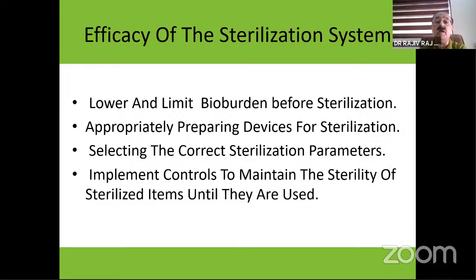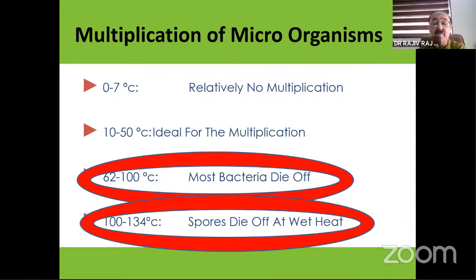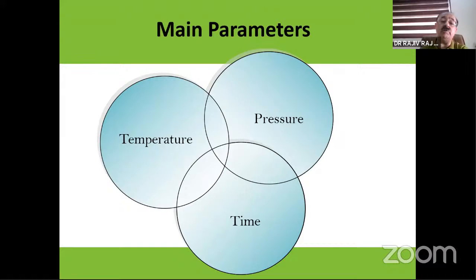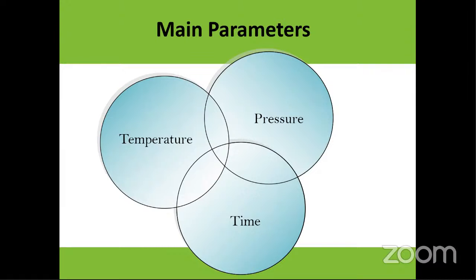One has to limit and lower the bioburden before sterilization. And then you have to prepare adequately and appropriately. Then you have to select the correct sterilization parameters, because different equipment require different parameters, and one has to implement controls to maintain the sterility of these items till they are used. So the magic figure that we want to know is 134 degrees at which the spores die in wet heat, and we'll come to the time control in a minute. All these autoclaves or sterilizing machines depend on the interrelationship of pressure, temperature, and time.